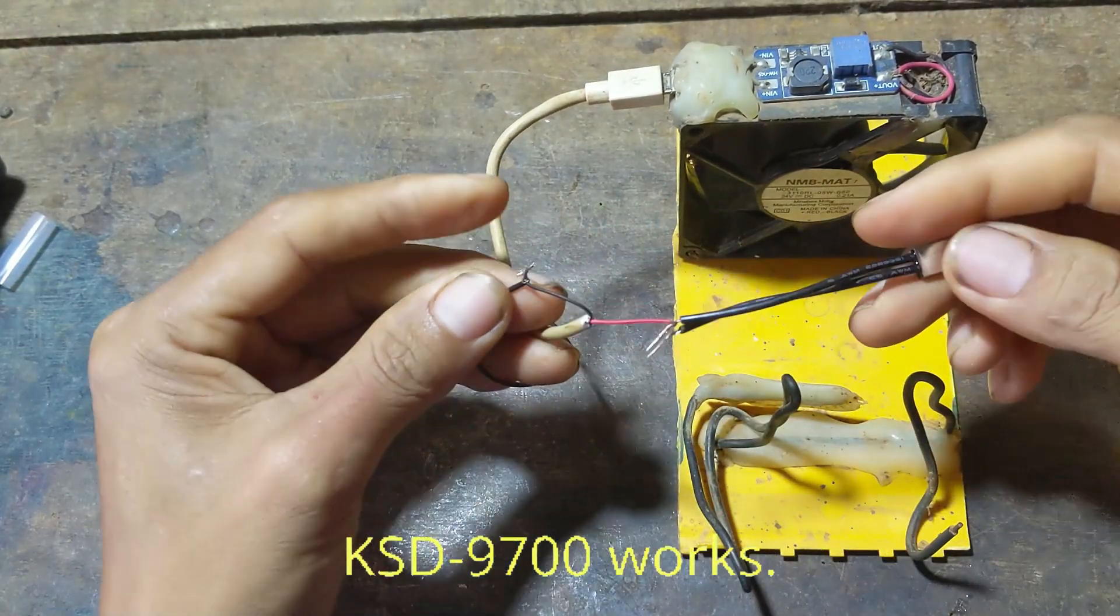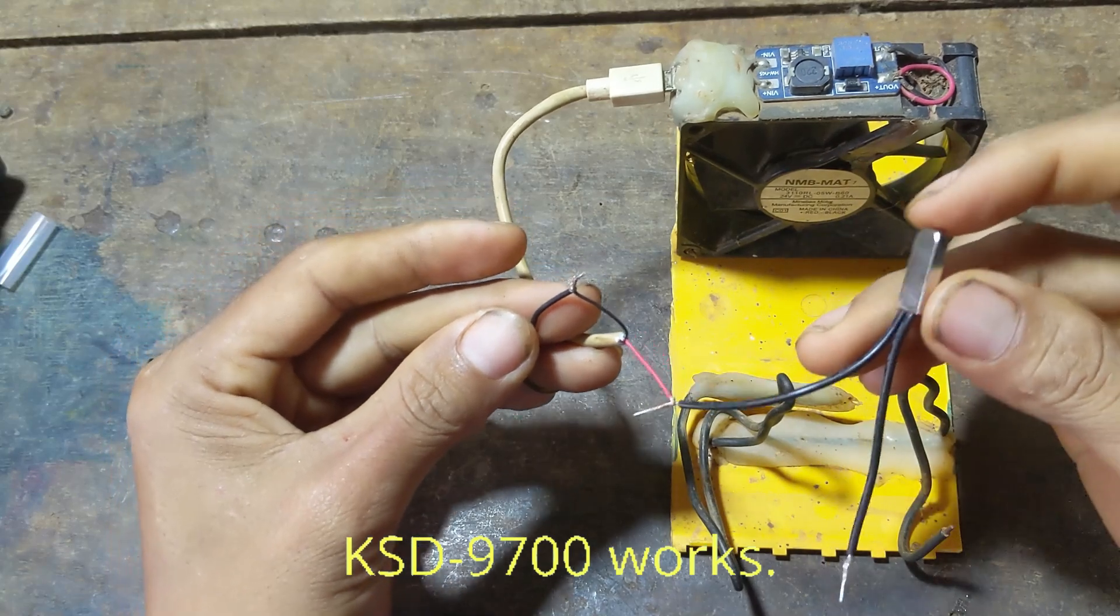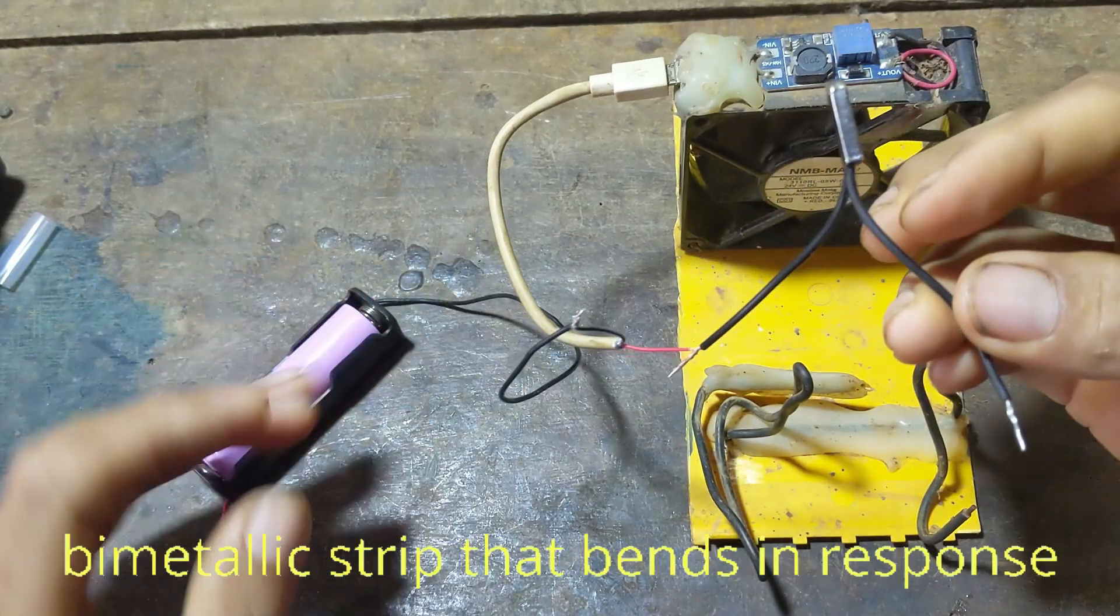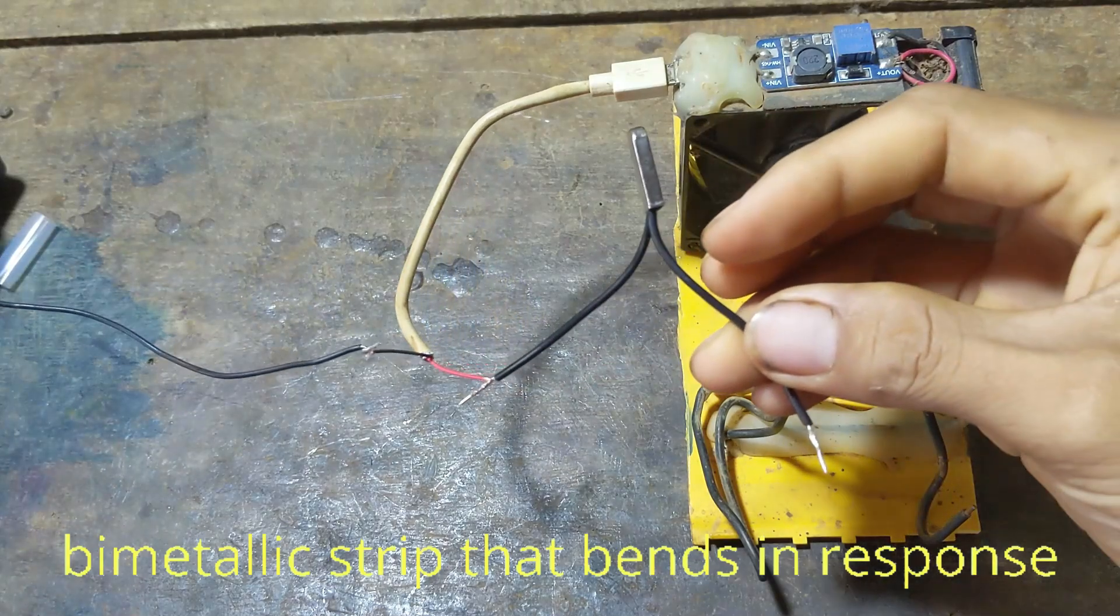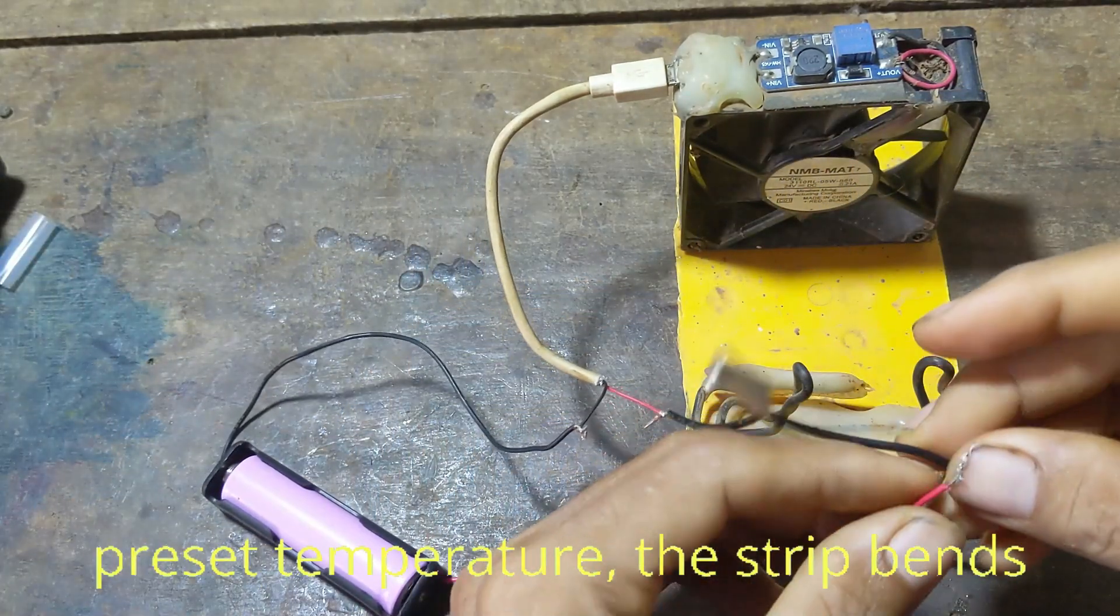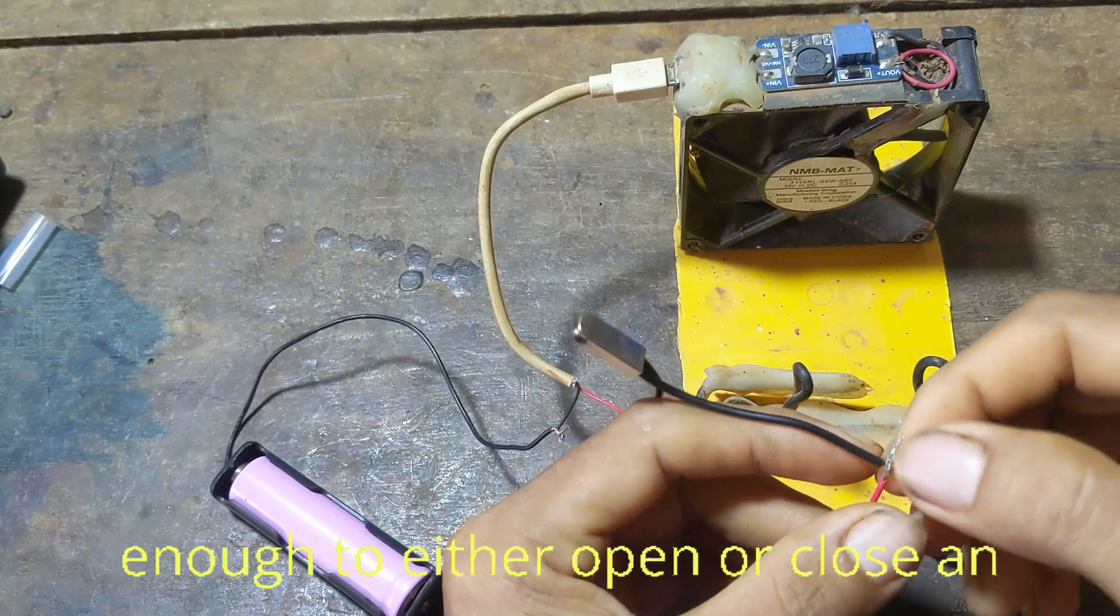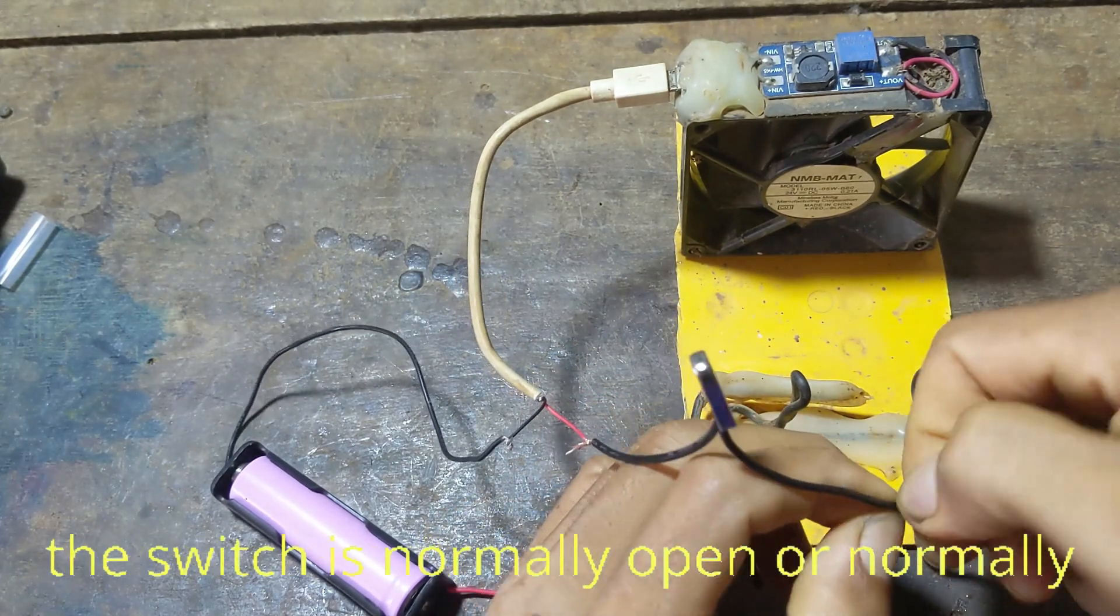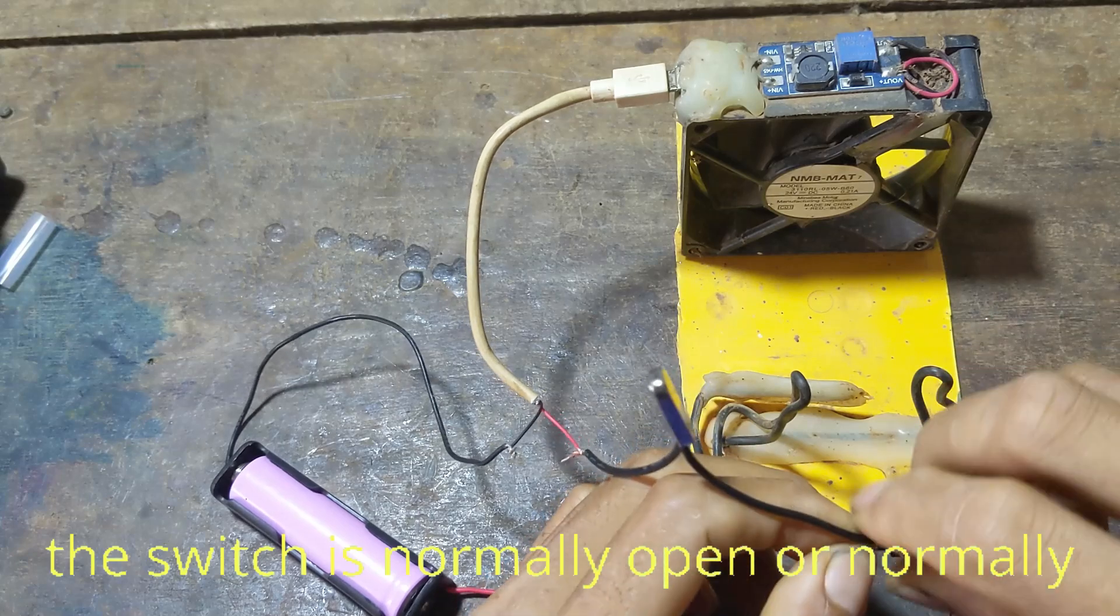How the KSD 9700 works? The KSD 9700 contains a bimetallic strip that bends in response to temperature changes. At a certain preset temperature, the strip bends enough to either open or close an electrical circuit, depending on whether the switch is normally open or normally closed.